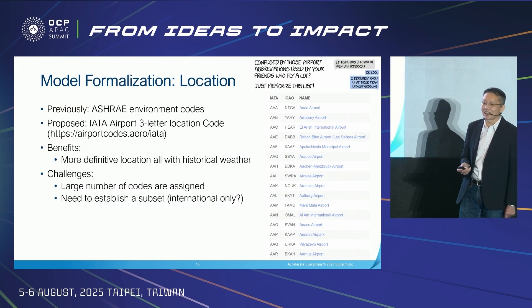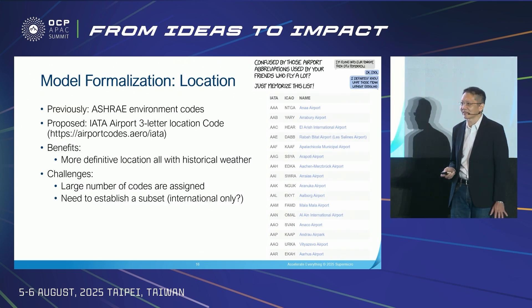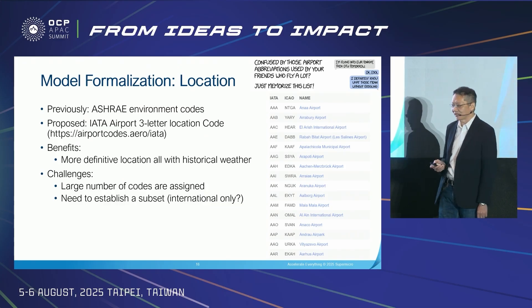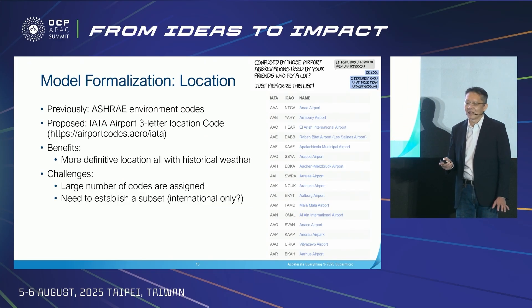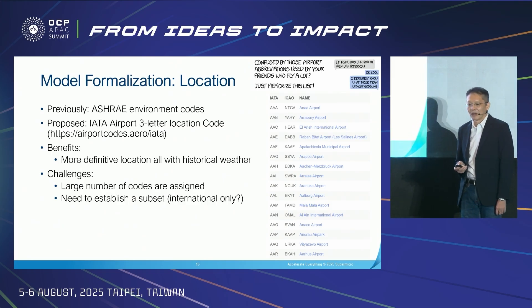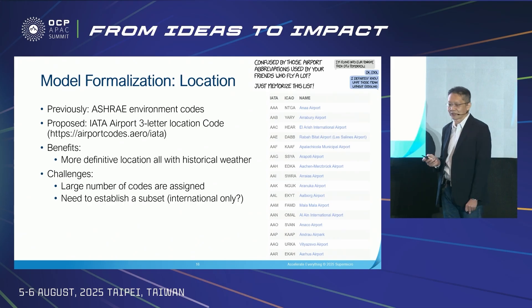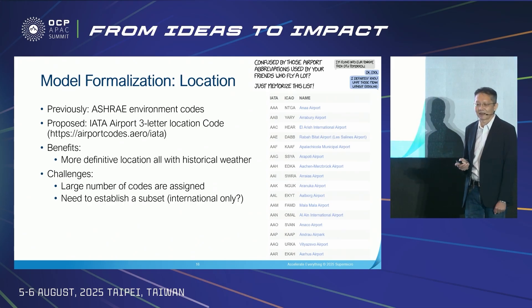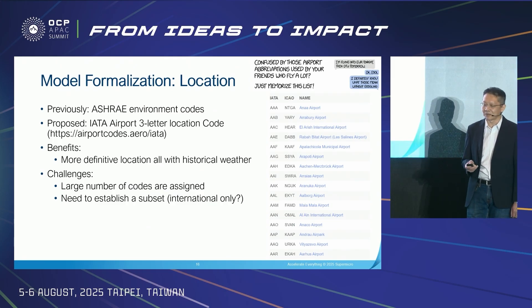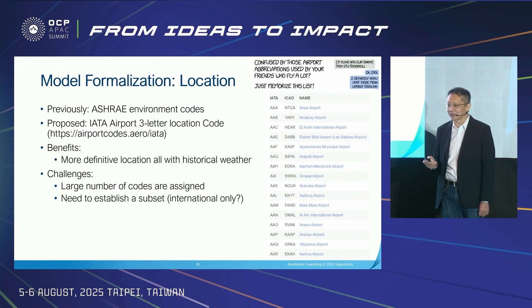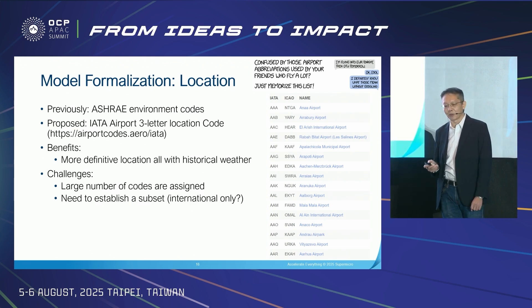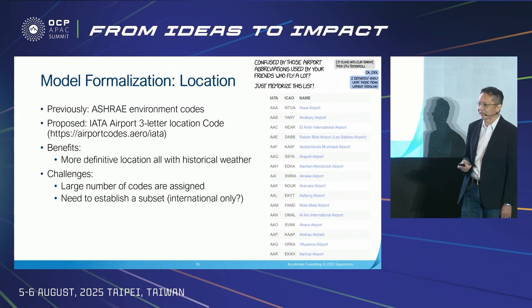Currently, we rely on ASHRAE environmental zones, which comprise 19 distinct climate zones. However, this approach lacks sufficient granularity. Chiller and economizer performance can vary significantly even within the same climate zone. To improve the accuracy of mechanical energy modeling, we plan to compile climate data from all airport weather stations, as these locations consistently maintain meteorological monitoring equipment. Users will be able to select the nearest airport to simulate conditions of a specific data center location.